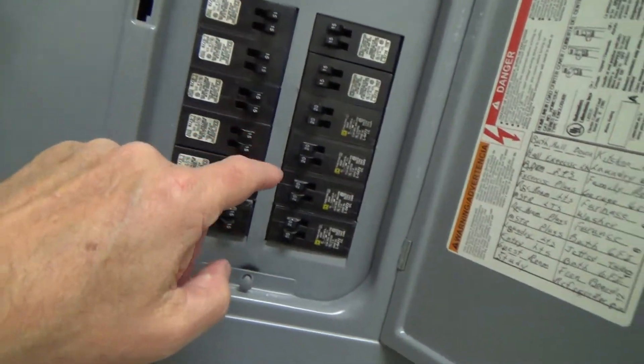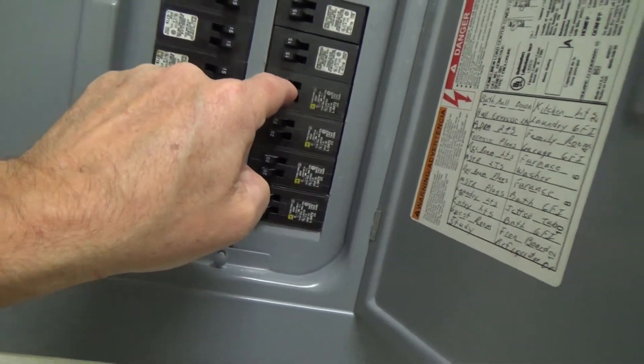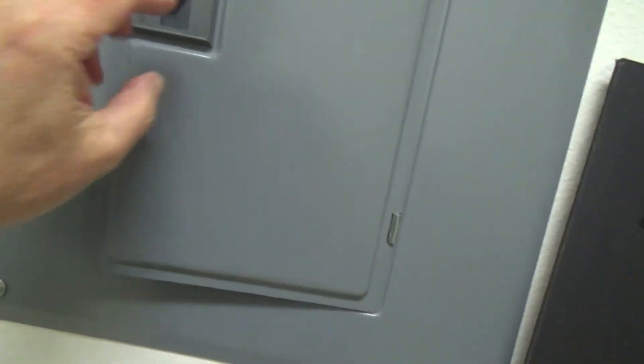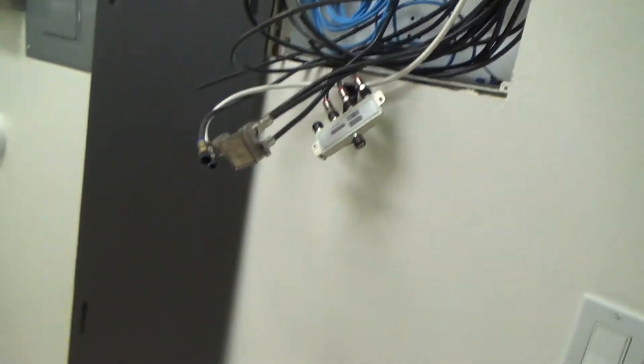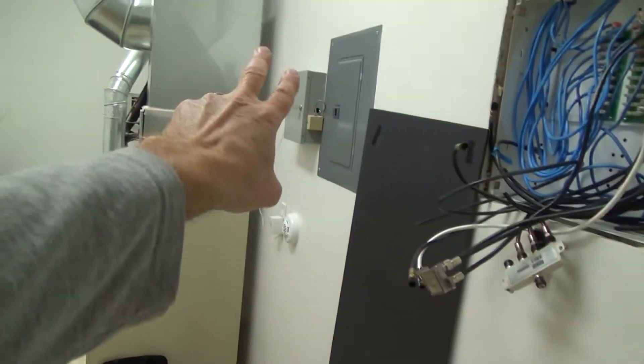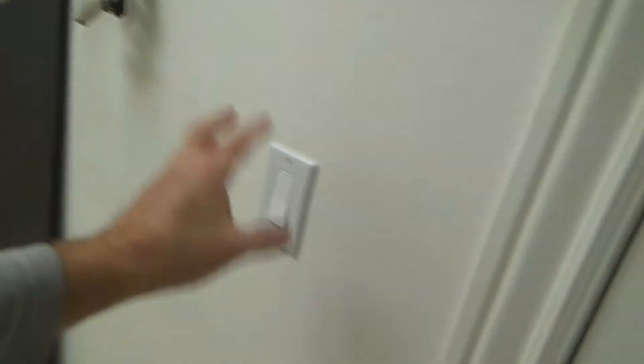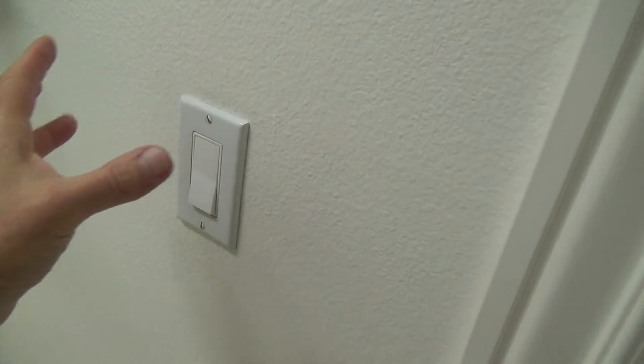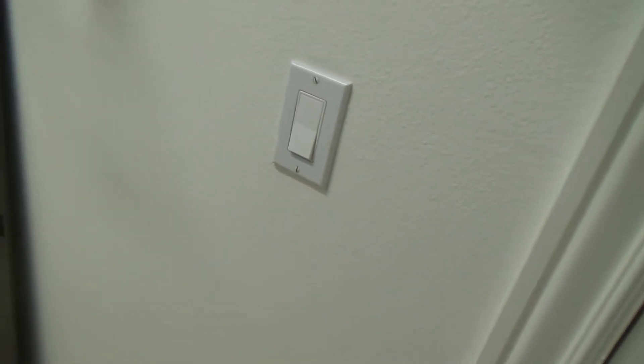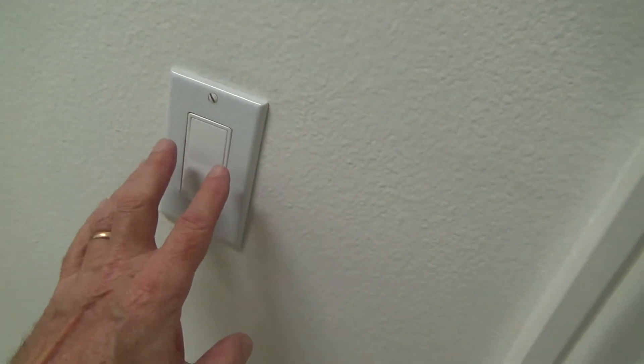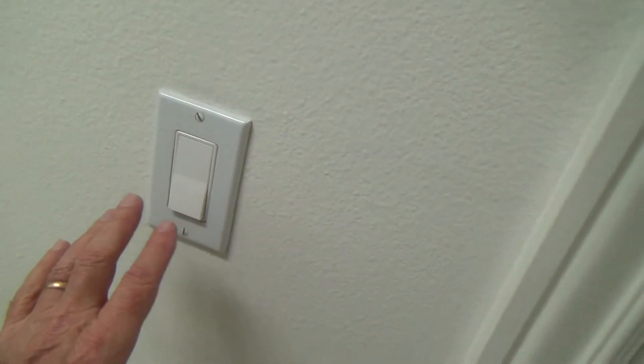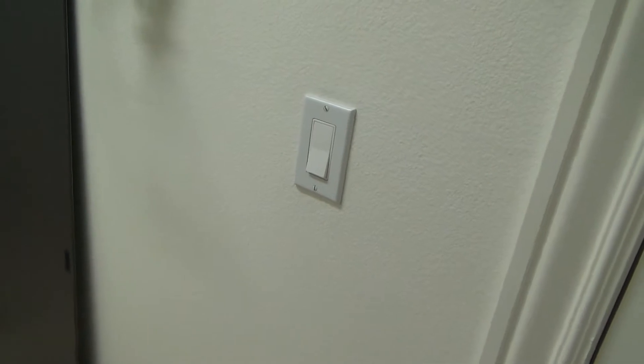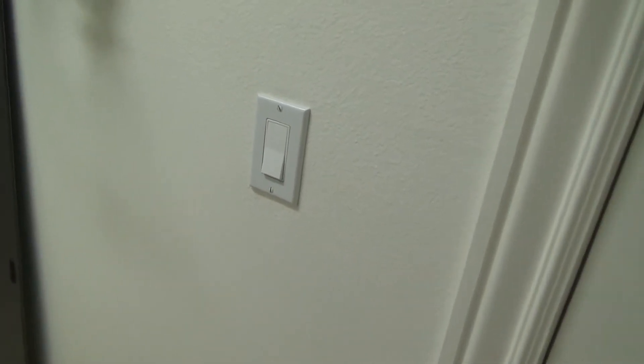But you can't run 14 gauge wire for 20 amp circuits. Does that make sense? You have to use for the 20 amp circuits, you have to use 12 gauge wire. You can't use 14 gauge wire. If you do that, you're under what it's going to be. So instead of the breaker tripping or something, if you're overloaded on the circuit, you might have a fire spark or something in your wall and have a fire start or something like that.